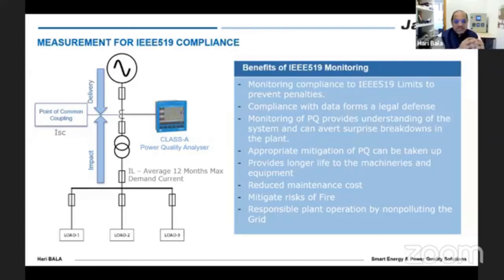When we do this, and we have the ISC by IL value, then we have a legal framework with Class A meters to show the utility whether we are complying with the IEEE 519 standard or not. And that's where Janitza also helps customers by creating a very conducive environment for understanding IEEE 519.